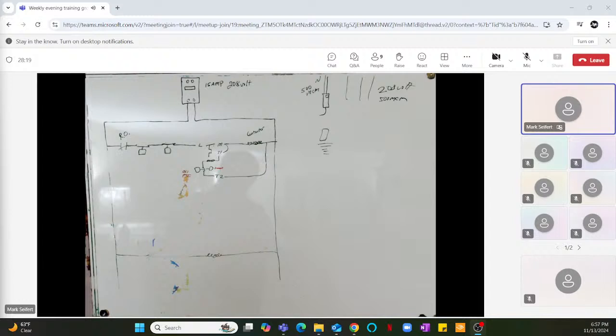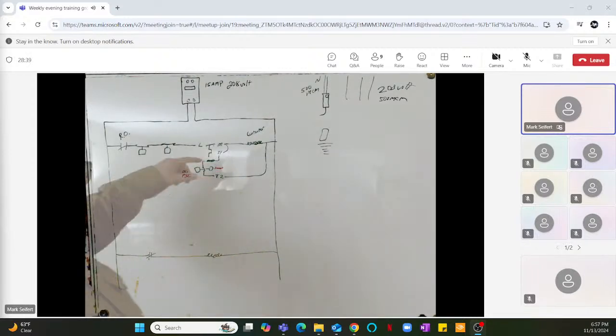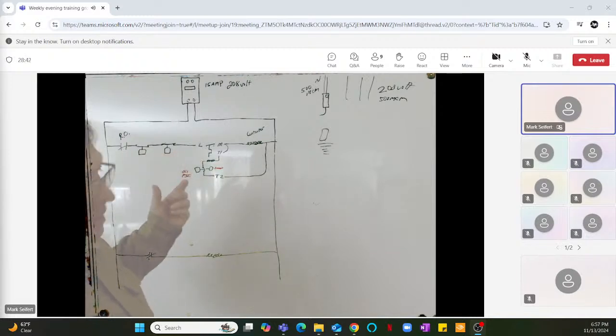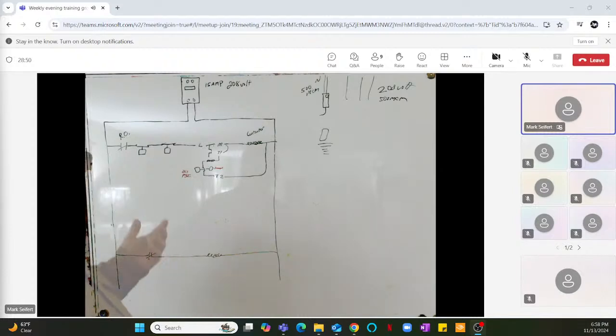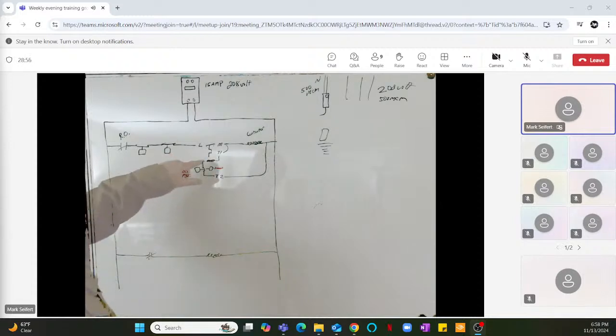If the oil pressure is higher than the sump pressure, it's going to open this circuit, not allowing current to flow through the heater. That heater is calibrated to give whatever amount of seconds the pressure control or oil control is rated for. Let's say it's a 90-second or a 60-second, whatever they are. I think they're 30, whatever the two are. I can't remember offhand. It doesn't really matter. But it's calibrated. Let's just call it 30 seconds.